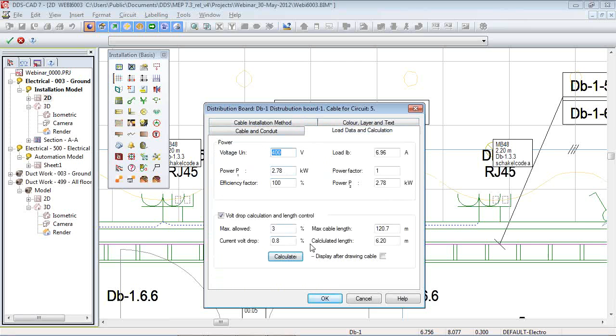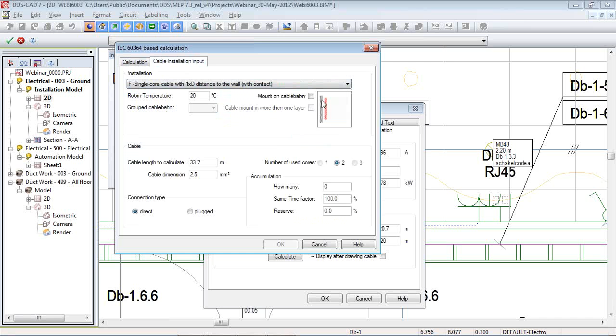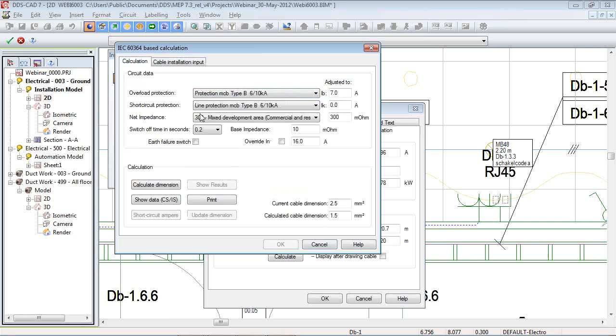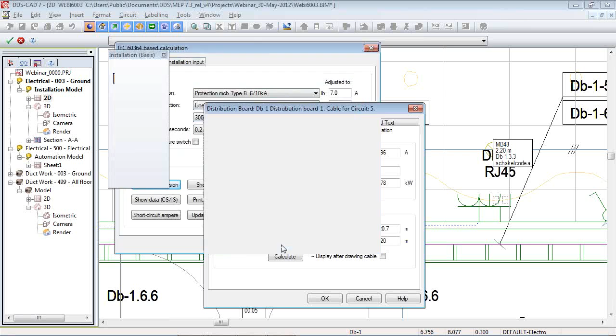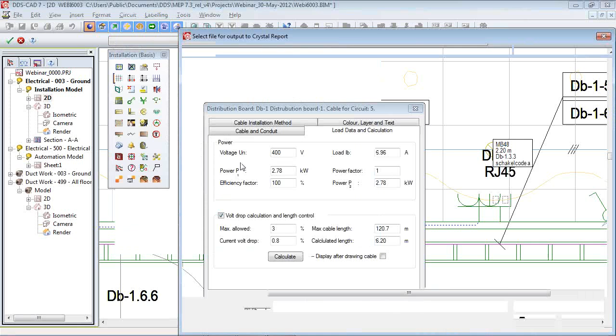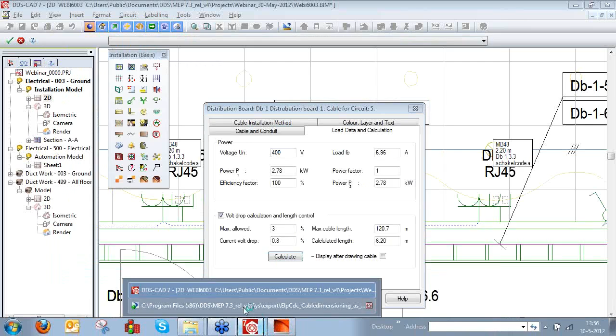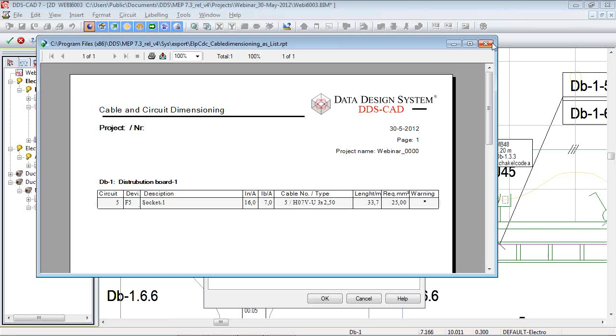So when I double click on a specific cable in here, we can have a load data, and we can use a function of calculating this cable. So from the maximum 3% of voltage drop, we can see that this cable length could be in the region of 120.7 meters. And we can now have a calculation and calculate the actual dimensioning by the use of an IEC 60364 based calculation. So from the results we do the calculation not only on voltage drop, but also on short circuit protection and also on overload protection. And of course, when changing one of the informations, like the diameter of the cable, so when I change it to 1.5, it will directly influence the maximum length of the cable.